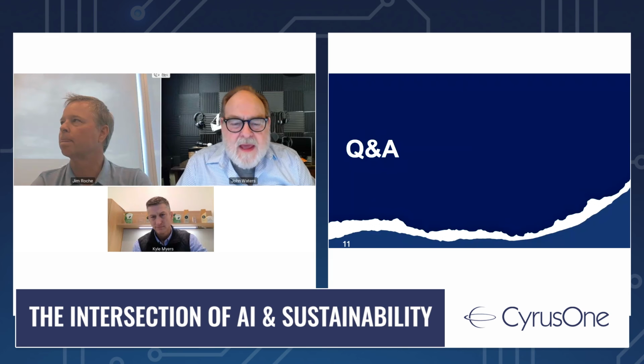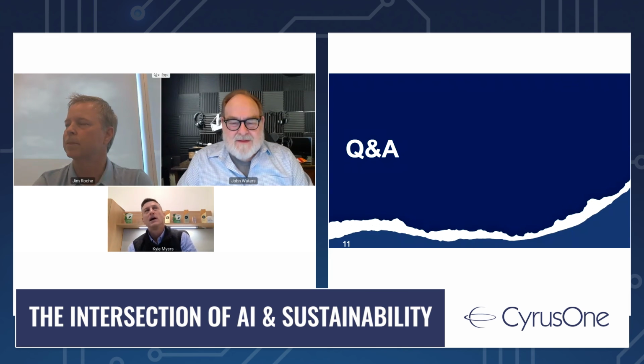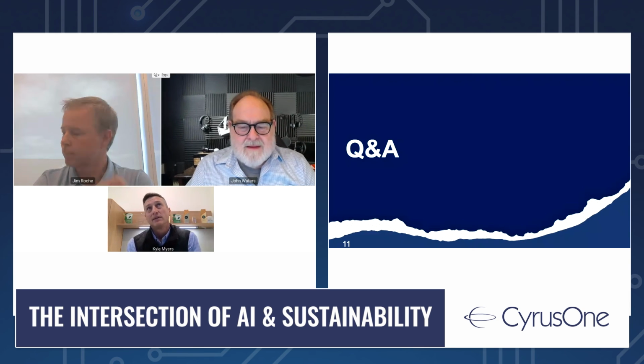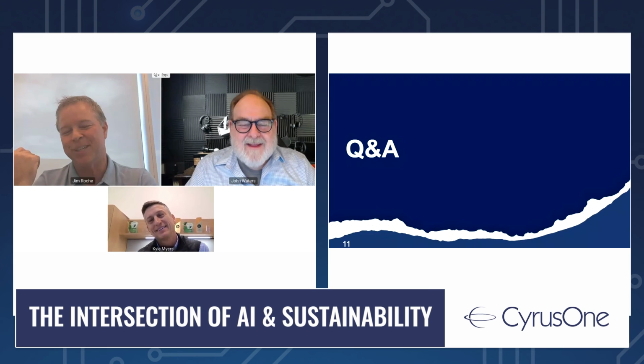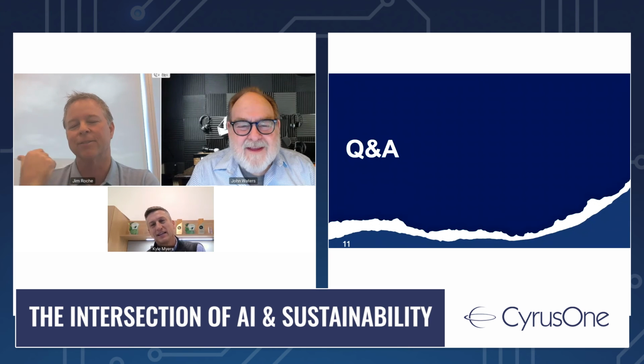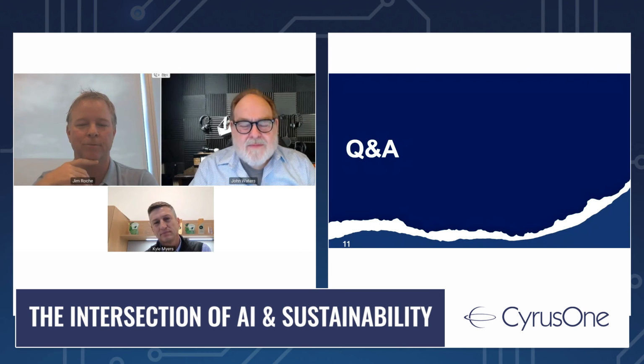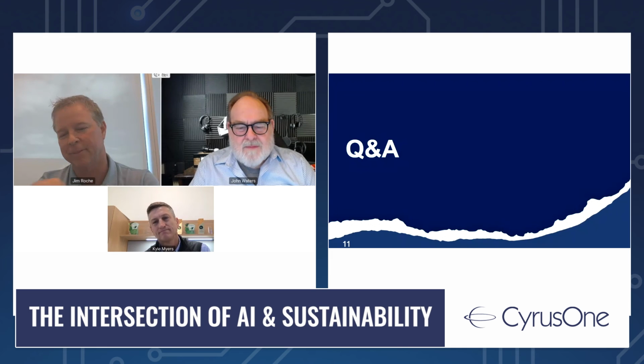Here it is: when thinking about PUE, CUE, and WUE, which should be the top priority as it relates to data center location? As it relates to location, I'd say there are two ways to think about that. Well, you can eliminate one, Kyle. Which one? The WUE for us isn't a big thing, since we're a closed loop system and don't use evaporation as a form of cooling for our data centers. You can take that one off, so now you're down to two.